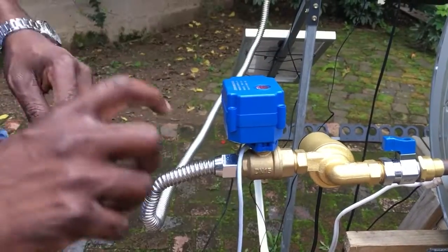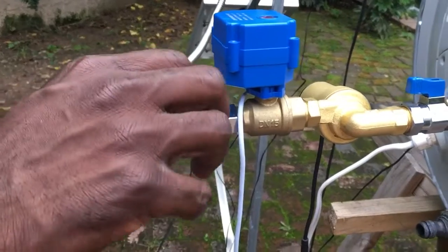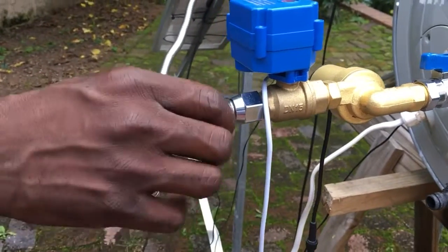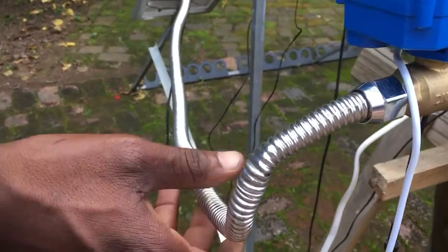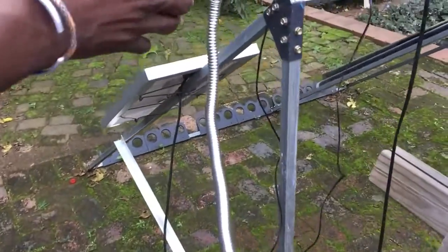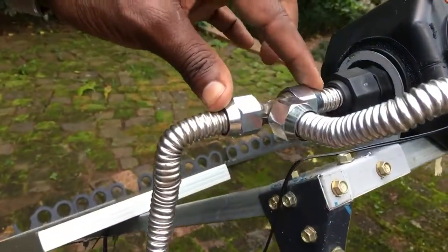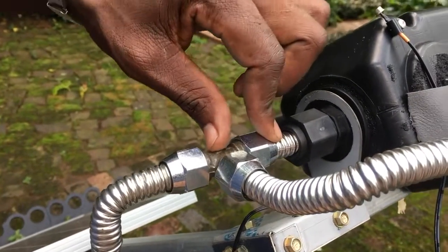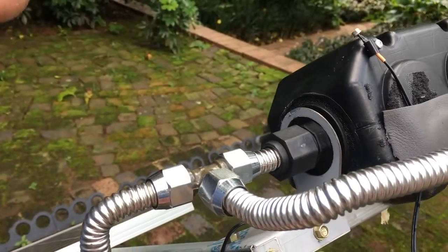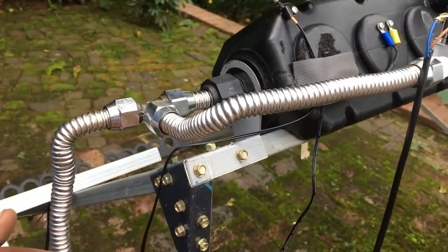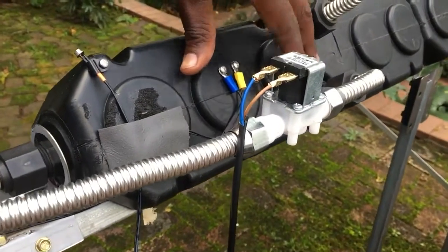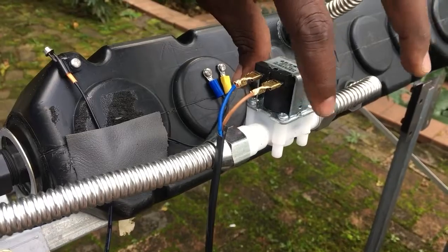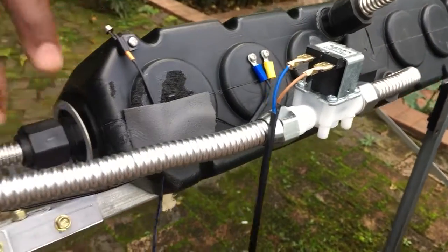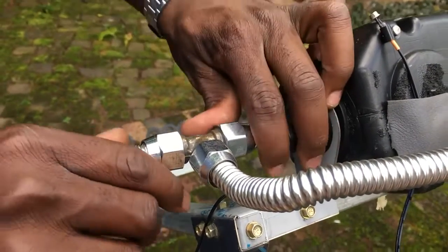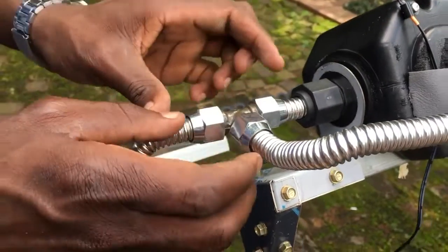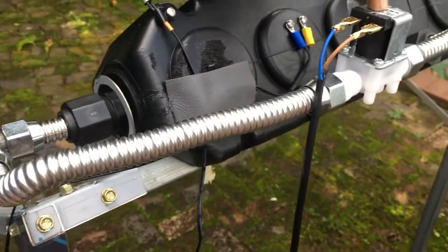After that, it's straightforward. You just connect the flexible stainless steel pipe, which goes to the cold side of the solar collector, whereby there is a T which splits the supply of water into the low pressure section in the manifold, which is controlled by the solenoid valve. And then the other one is for the heat exchanger. So that's the most important thing. The cold water side, that's where the solenoid valve should be.